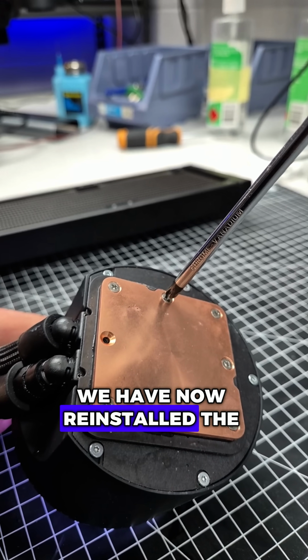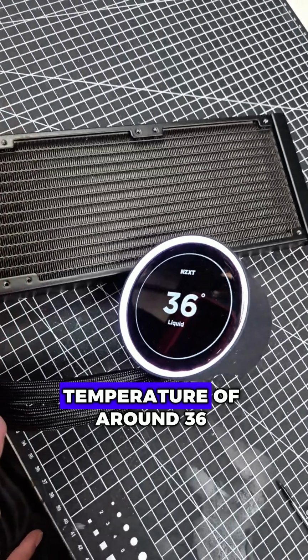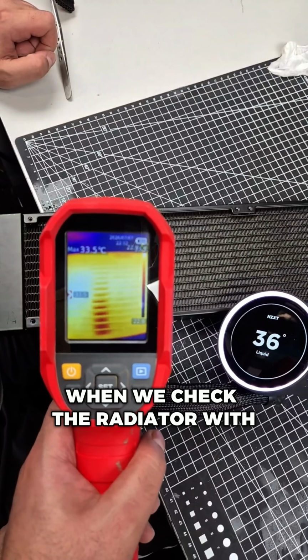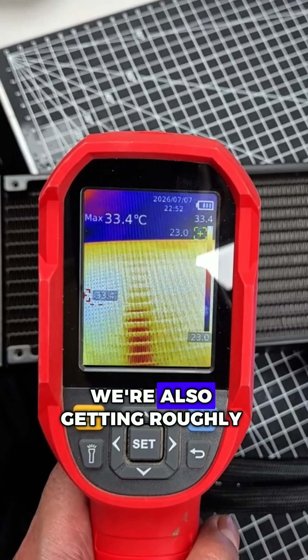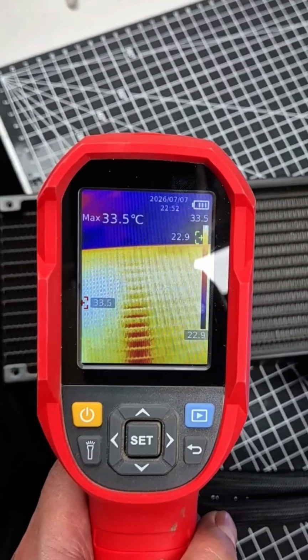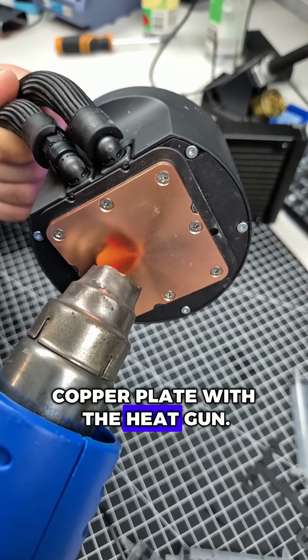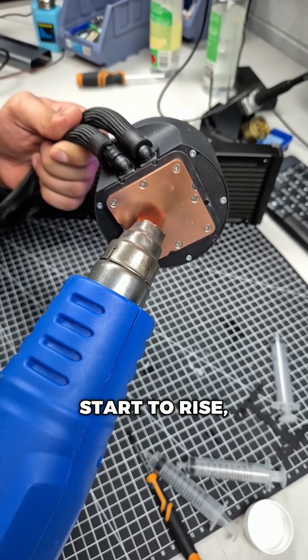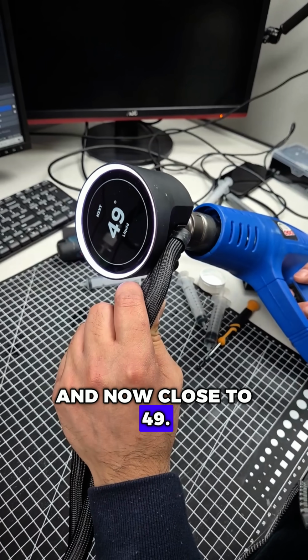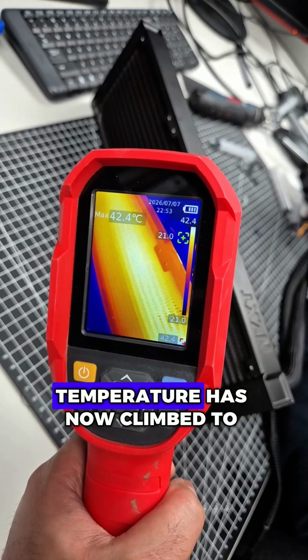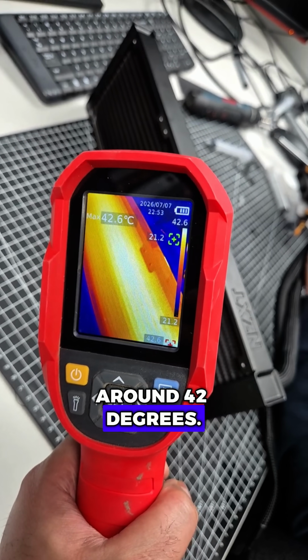We have now reinstalled the copper plate and the system is showing a temperature of around 36 degrees. When we check the radiator with the thermal camera, we're also getting roughly around 36 degrees. Now we're going to heat the copper plate with the heat gun. You can see the temperature start to rise, now close to 49. And yes, the radiator's temperature has now climbed to around 42 degrees.